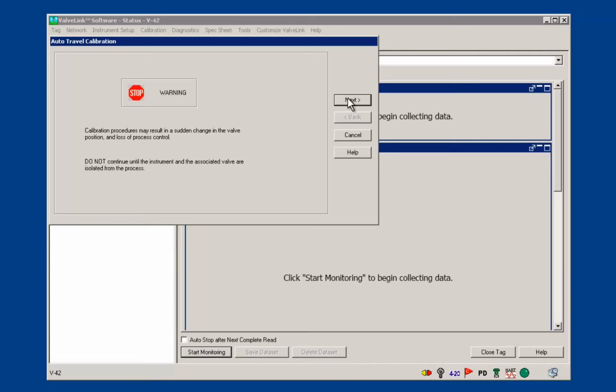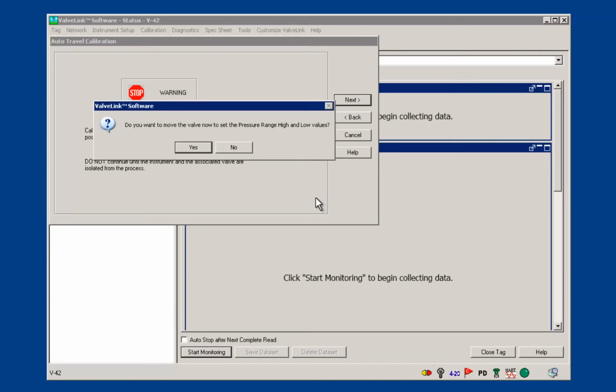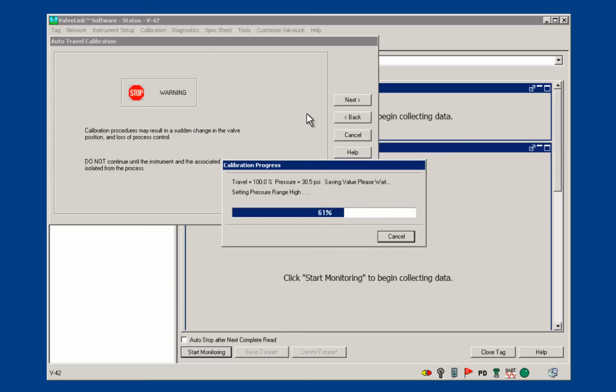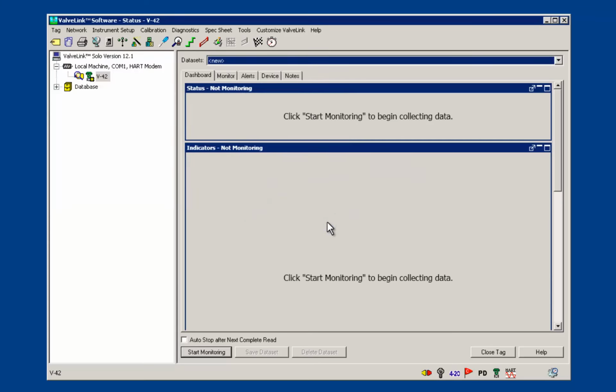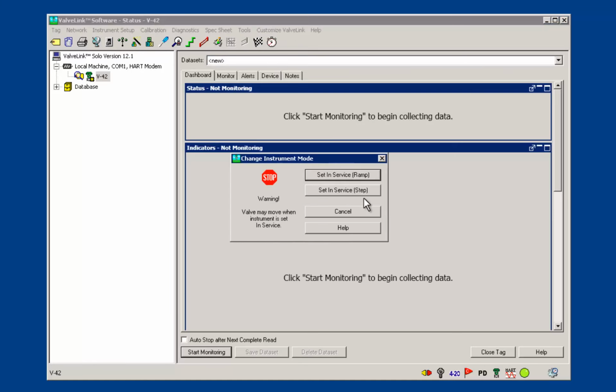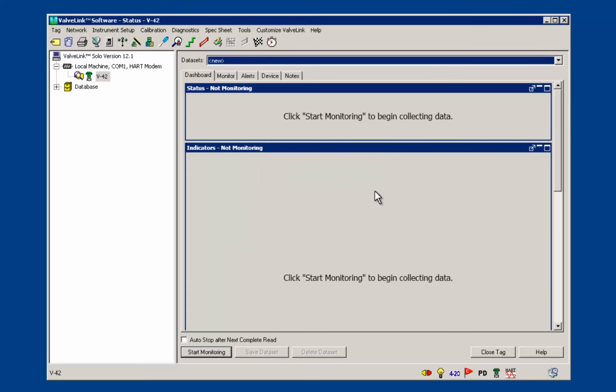Once that process is complete, you can choose to move the valve to set the high and low values for pressure fallback options. ValveLink will now calibrate the device for you. Lastly, remember to place the instrument back in service by clicking the Instrument Mode button here and then clicking Set in Service. Your FIELDVUE DVC6200 digital valve controller has been successfully configured and calibrated.